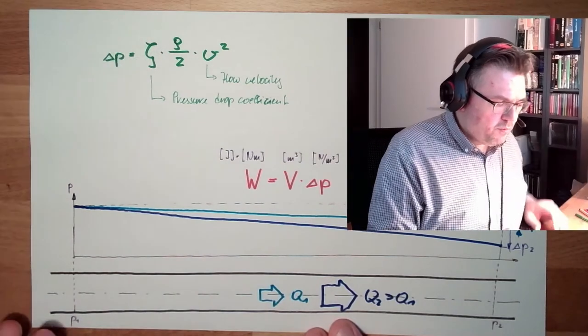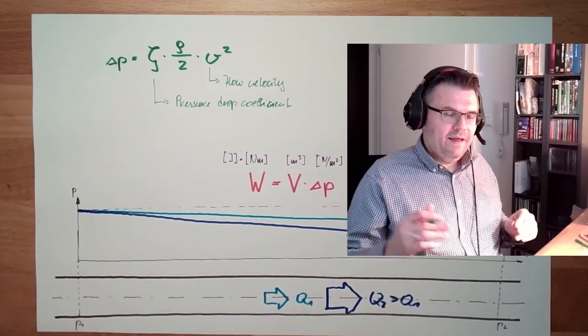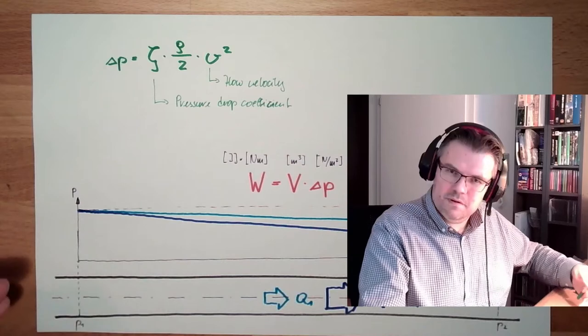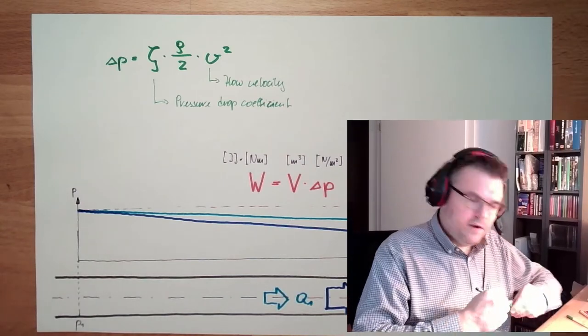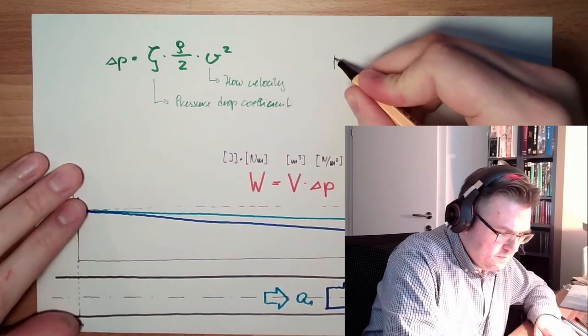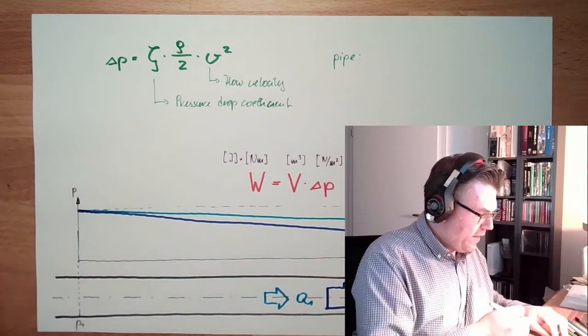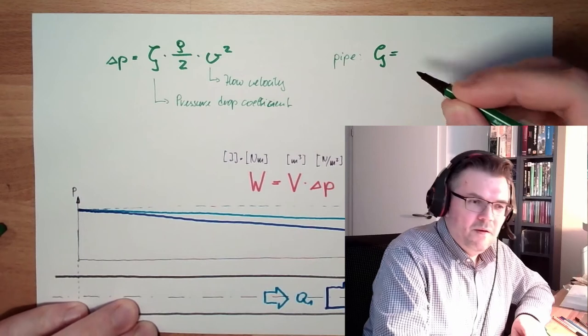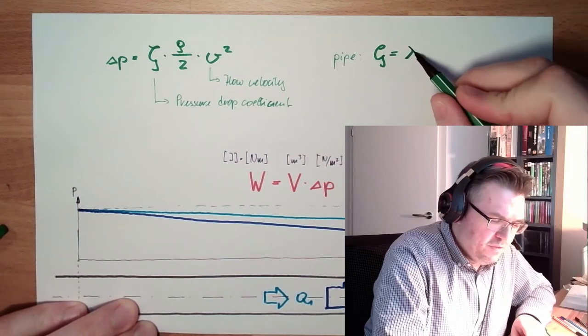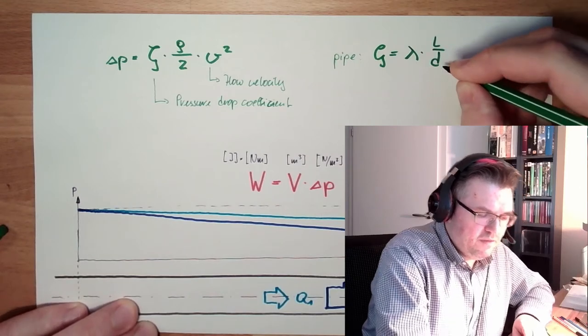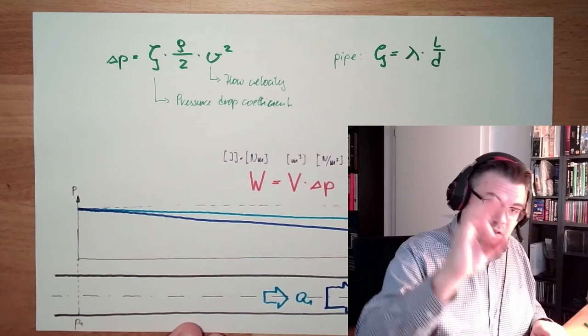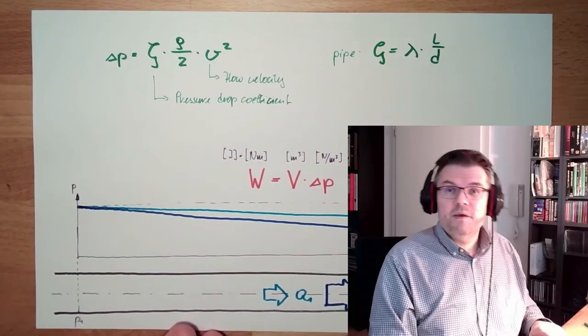From what things is this pressure drop coefficient depending? Well, on a pipe, we can calculate this pressure drop. We can calculate this pressure drop coefficient. Again, there is the so-called pipe friction coefficient, lambda, multiplied by the length of the pipe divided by the diameter. This means the longer the pipe is, the more pressure loss I can expect. And the smaller the diameter is, the more pressure loss I can expect. Clear, right? If you think about the water hose in your garden maybe. If you have a short hose, the pressure drop is not that severe. If you have a long hose, then the pressure drop is much severe.